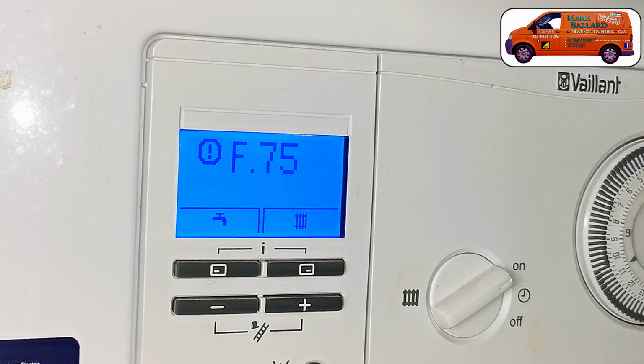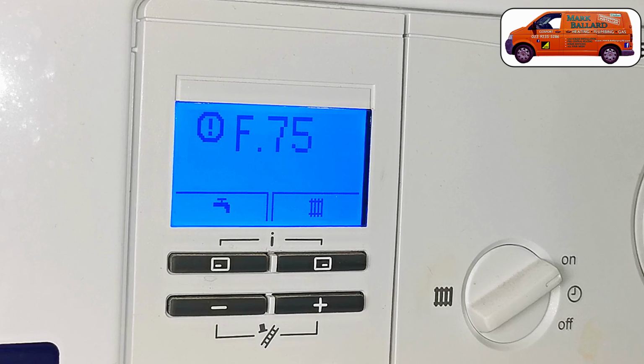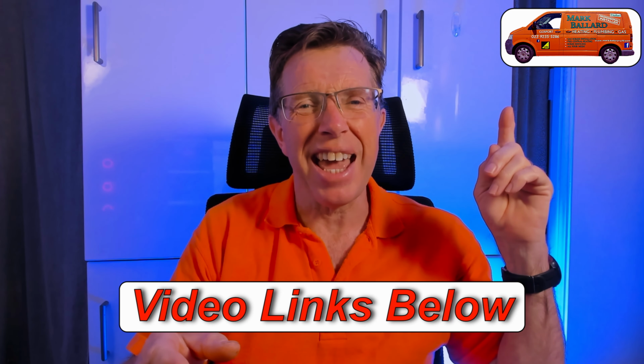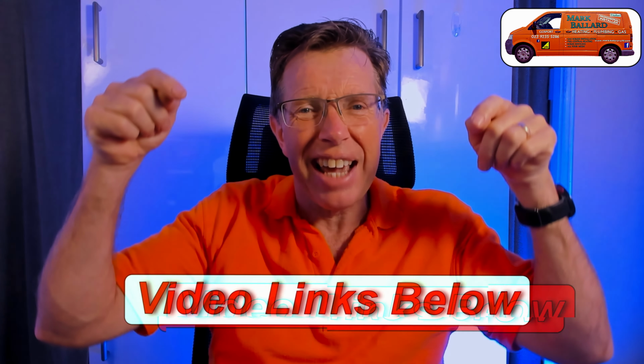position. Now if you do have a faulty pump, it's most likely that you got F75 come up in your display. I want to let you know that F75 fault can come up for lots of different reasons, not just a faulty pump. So before you go buying a really expensive pump, make sure that you've checked out the other causes that you may be getting the F75 fault for. And of course, I've made lots of other videos all about the F75 faults.